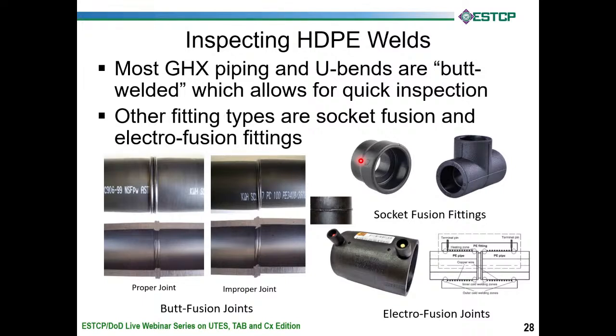And another type of fitting that's used sometimes in the geothermal industry is down here. This is sometimes called electrofusion. The fitting literally has two electrical connections here. And if you can see, there are some heating elements in here. And so you literally heat up the fitting there by hooking it to a machine. It's nice because it's low. As long as the people in the field get the fitting clean, then it does apply the exact amount of heat, and you can log it with the machine, and it can give you a full record, even with GPS coordinates of where they are.